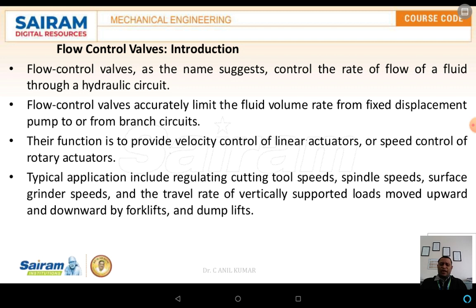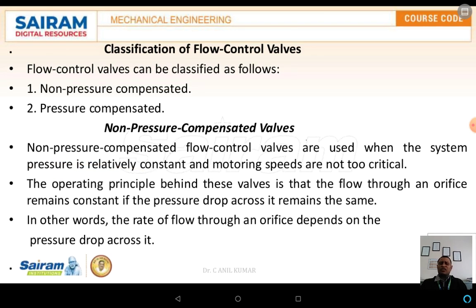Flow control valves provide velocity control of the linear actuator or speed control of the rotary actuator. If the flow is maximum, the linear movement of the actuator will also be more, and the speed of the rotary actuator will also be more. If the flow is less, the speed of the linear or rotary actuator starts decreasing. Typical applications include regulating the speed of actuators, especially in the automation field.